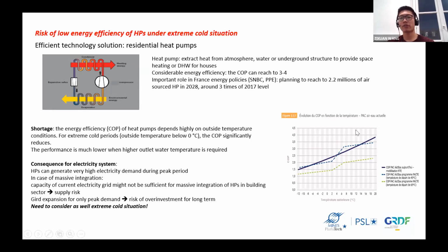However, the main shortcoming of heat pumps is that their energy efficiency is highly dependent on outside temperature, and under extreme conditions, the coefficient of performance will significantly reduce, as presented by the figure on the right. When the temperature is below 2 degrees, the coefficient of performance is always under 1.5. Of course, it depends on the outlet temperature of water.